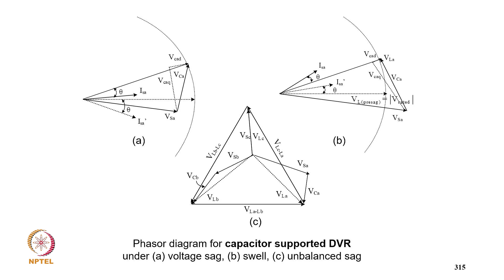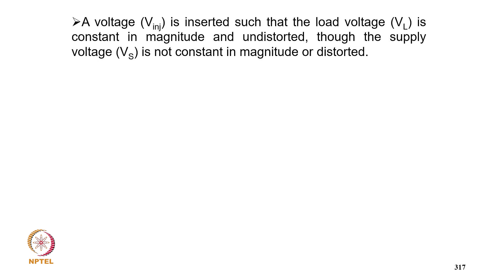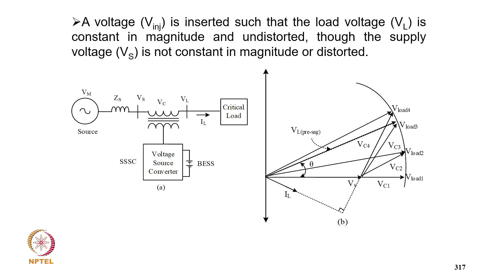Now coming to the principle of operation of DVR, the voltage is injected such that the load voltage VL is constant in magnitude and undistorted, while the supply voltage is not constant in magnitude or is distorted. So this is typically a battery supported voltage source converter as a series compensator, and from source to load you should be able to inject the voltage at any angle, but with the minimum current going to the critical load. And this is the way we can regulate the voltage.